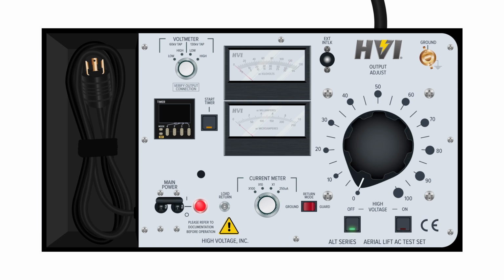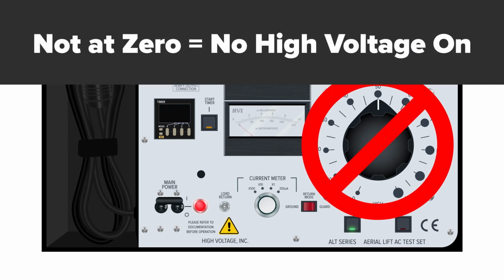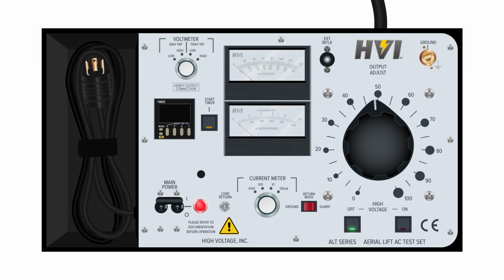The output dial also functions as a zero-start interlock, one of two safety features for the device. The output dial must be at 0 to energize the high-voltage circuit. With a zero-start interlock, the high-voltage circuit cannot be energized unless the level of voltage is initially dialed down to 0. ALT series units also have an external interlock, the second of the two safety features for the device.